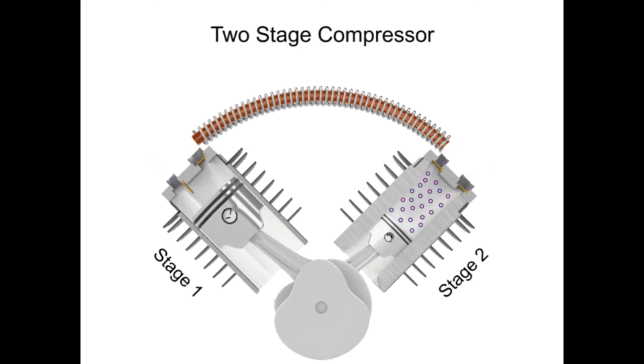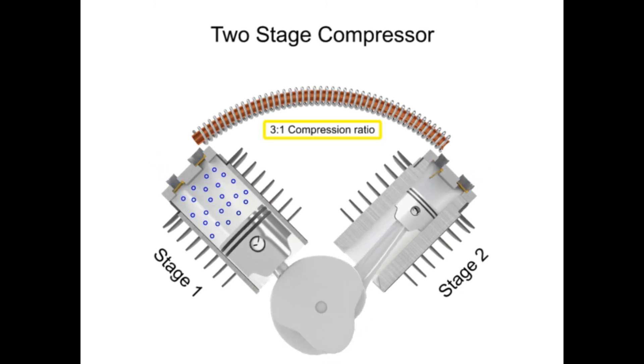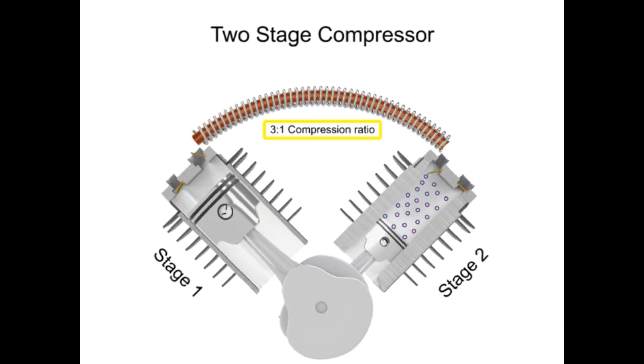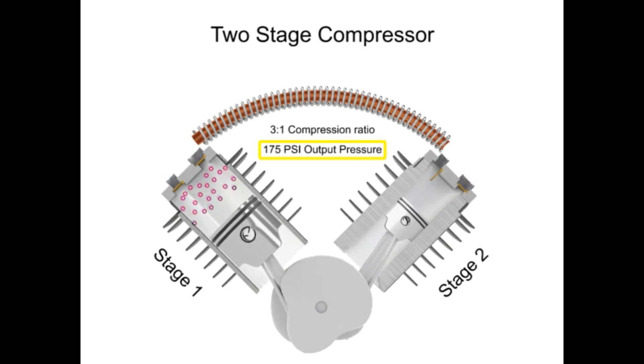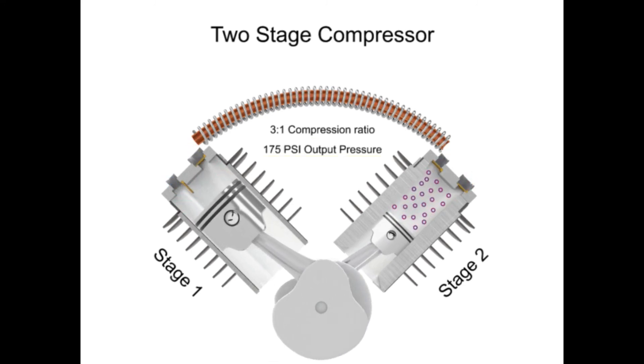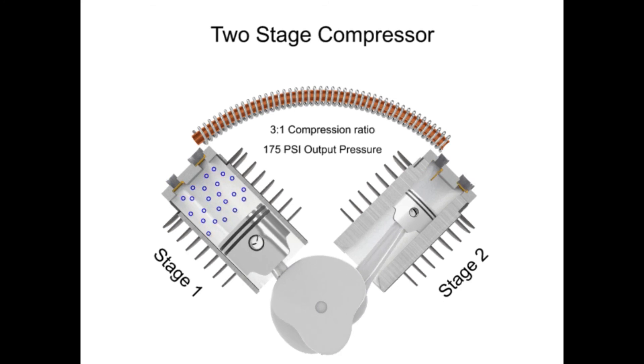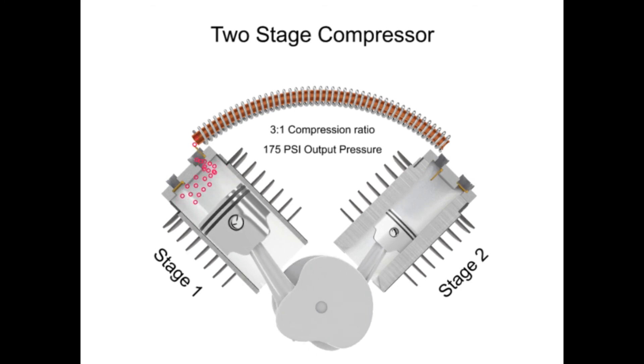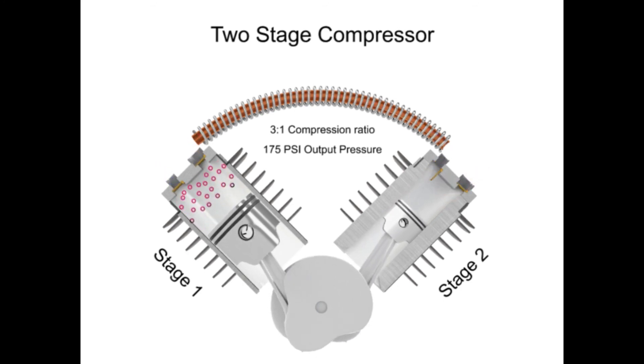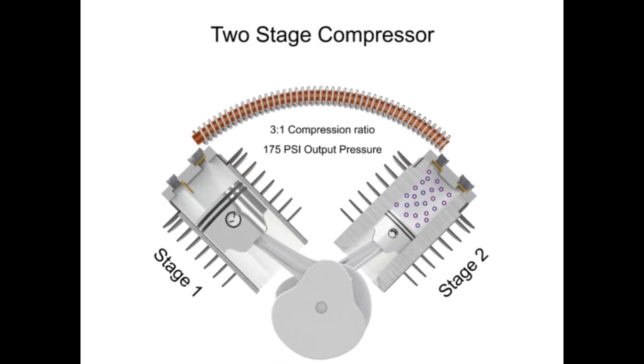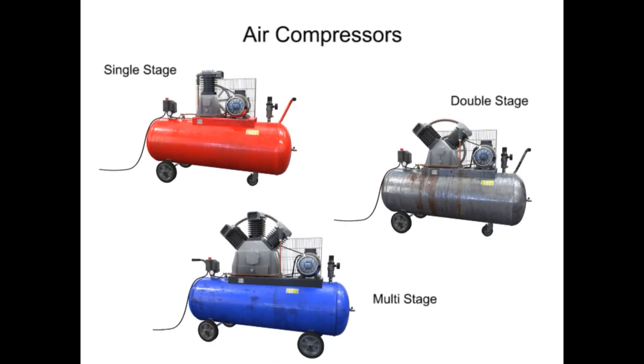Two-stage compressors have a compression ratio of 3 to 1 or even less per stage, but can operate up to 175 PSI. They can also deliver more air at a higher pressure than single-stage compressors of the same horsepower. If pressures of more than about 175 PSI are needed, multi-stage compressors should be used.